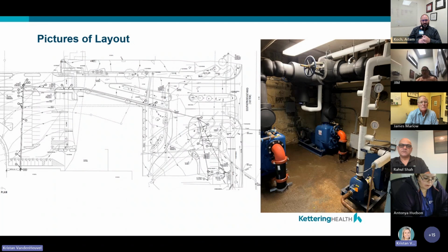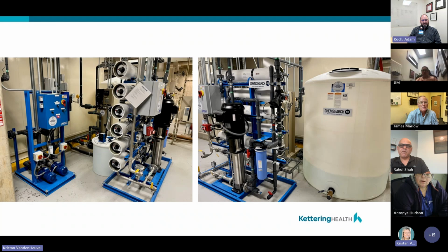Next slide, please. Here's a picture of it. On the left side are the transfer pumps. One thing we learned with the transfer pumps is we really need to make sure those are on VFDs, because when pumps come on, they slam the water as hard as they can. So we had to build that water up and slow it back down when shutting it off.